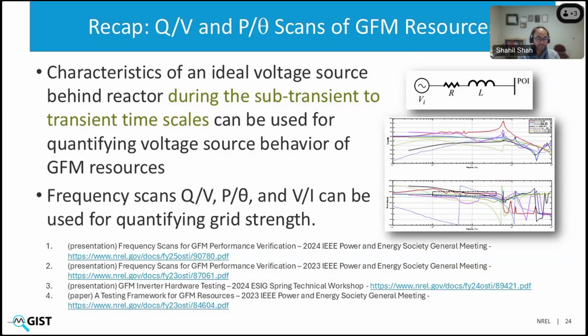We have made several presentations and papers on how to quantify the voltage source behavior of grid forming resources using Q by V and P by theta scans. Basically, they are scans of the transfer function from voltage magnitude to reactive power output of the grid forming resource, as well as from the phase of voltage at the POI to the active power output. And these scans can show you quantitatively what the voltage source behavior is, or what grid strength the grid forming resource is providing.